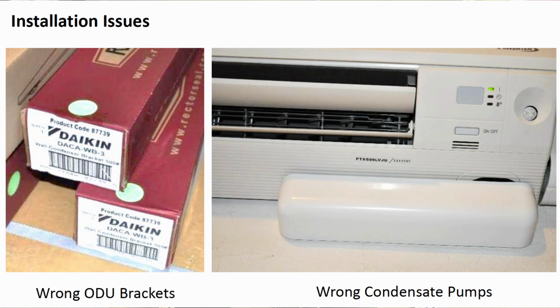Yes? And the condensate pumps push the moisture back out from the units, correct? Yeah, when you're in cooling mode in the summer and you're pulling humidity out of the air, that humidity has to go somewhere. With a window AC, it gets thrown into the fan on the outside, it's called a slinger ring, and it goes onto the condensing coil and slightly improves the efficiency of the system. You can't do that with this. So you have to have a place for the condensate to collect, and then you either drain it directly outside, or you have a pump to send it somewhere. We'll talk a little more about that later.